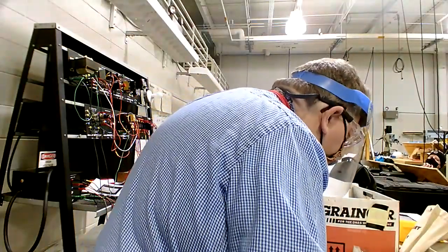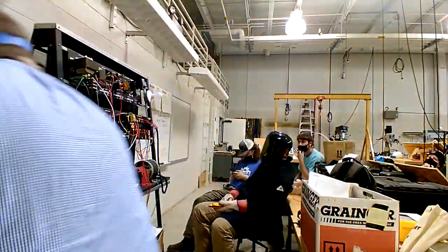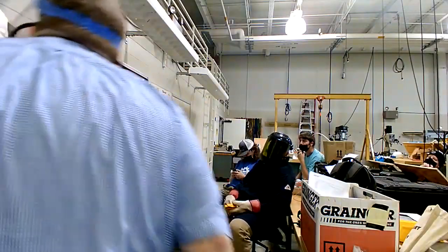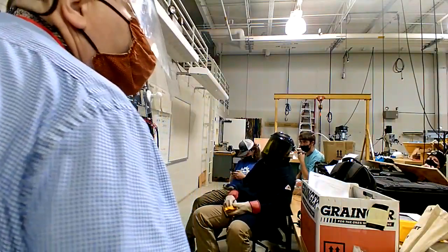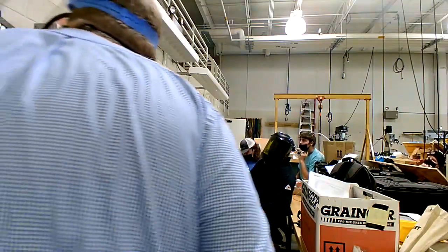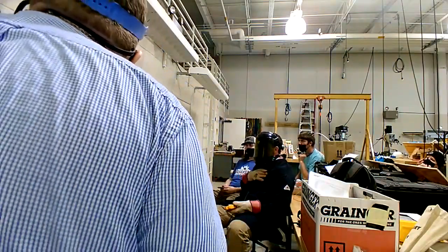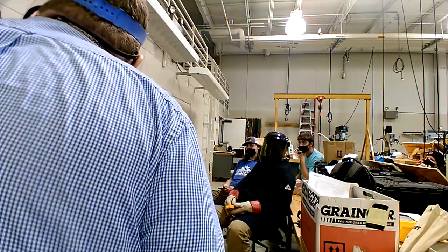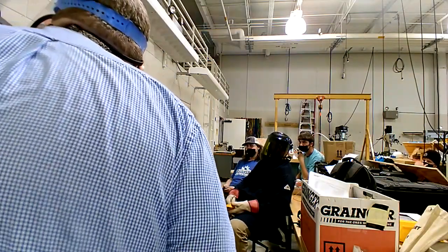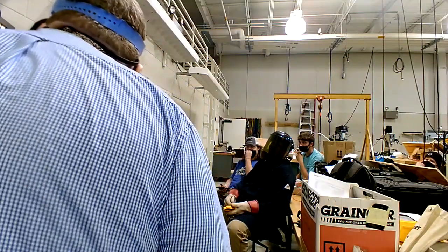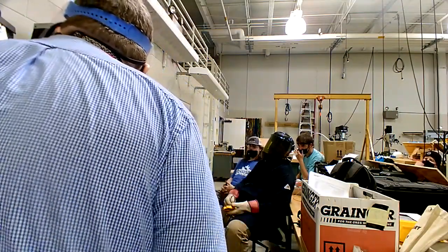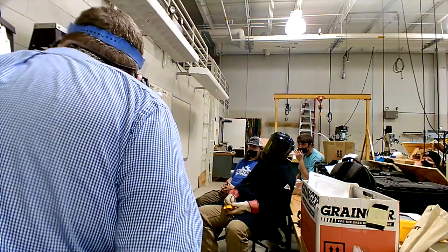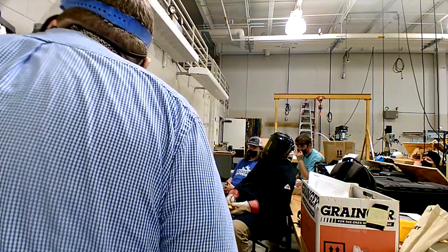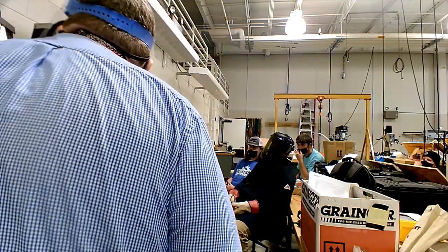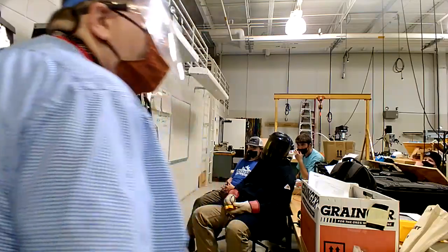Now here's our subject, guys. You look right up here. This is going to be very, very brief, but very important. Everybody watch it. When we step our voltage down from 208 or whatever it is down to 120, we have our hot wire, and it goes to whatever controls we have. And then on our neutral side, coming from the starter and the overload, we go back to the transformer. Then we also ground that neutral leg, right?